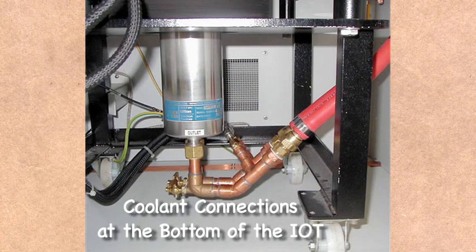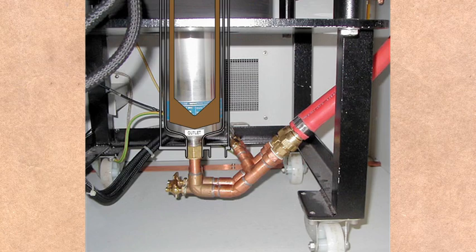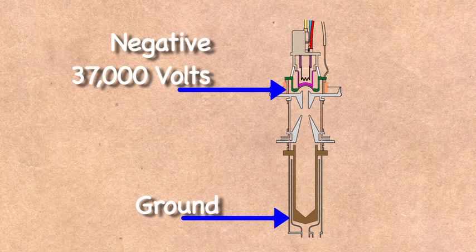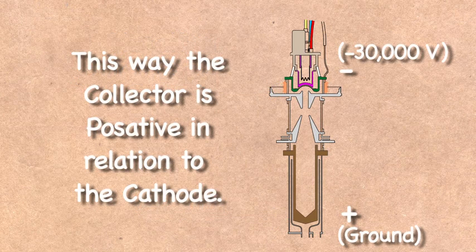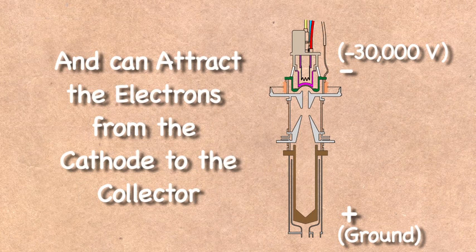Because the collector is in contact with a flowing coolant, it needs to be at ground potential. In order to make the collector/plate positive relative to the cathode, the high voltage negative lead is attached to the cathode where it sits at a negative 30,000 volts, while the collector remains at ground potential.